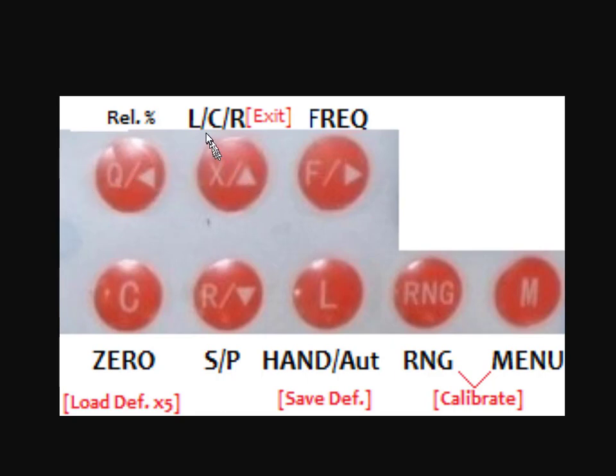The X button is equivalent to L, C or R, so you can choose between measuring each of those different types of component. The frequency button, C button is actually 0, so that's the one used to set the compensation for the probes. Series and parallel button is marked as R. Hand is actually the manual mode, so this is where you can change the internal measurement range. Range and menu buttons are fairly obvious. And the notation in brackets here is what the buttons do when you put it into calibration mode.